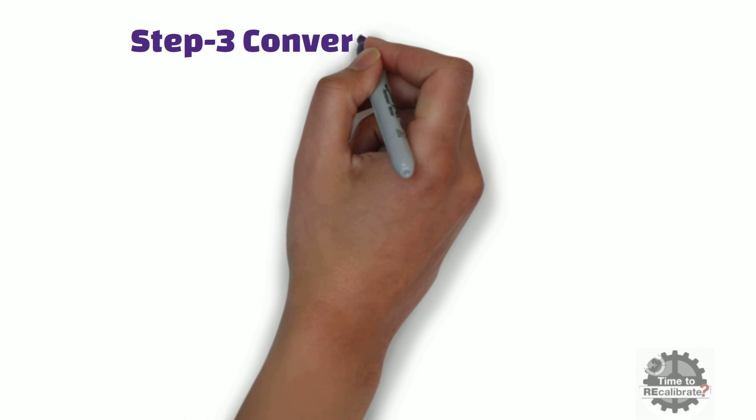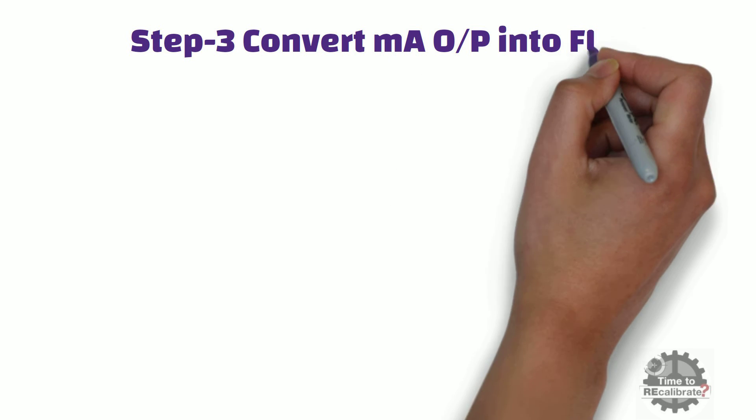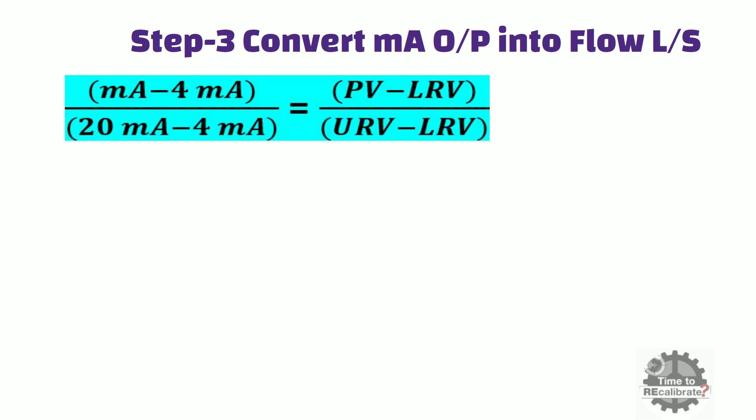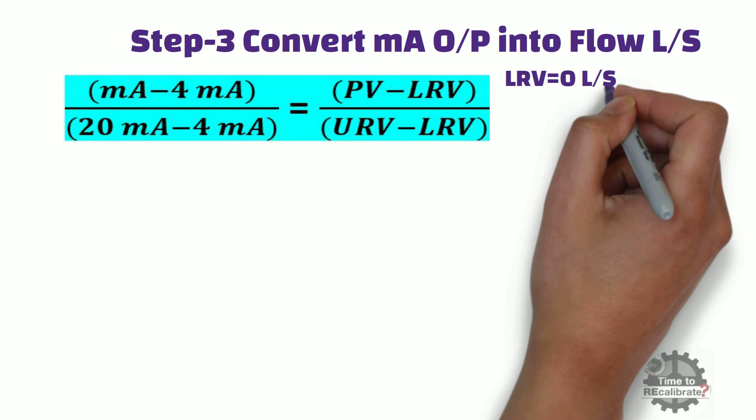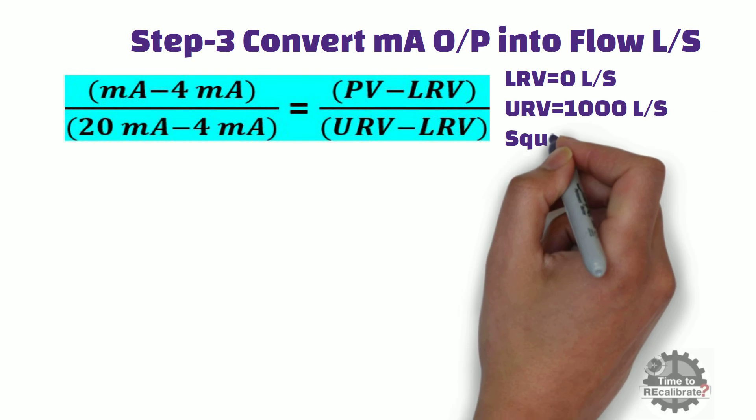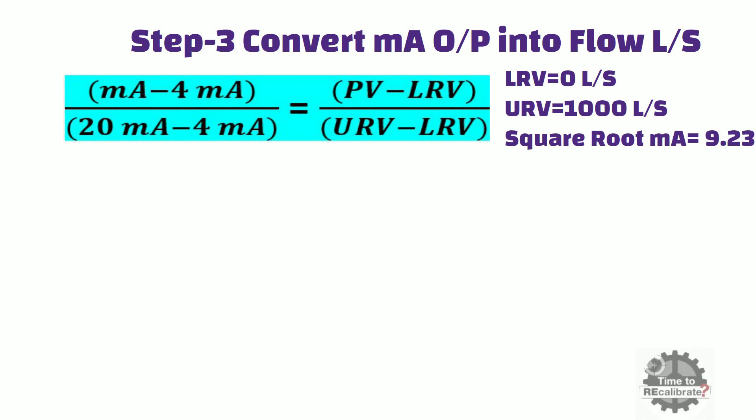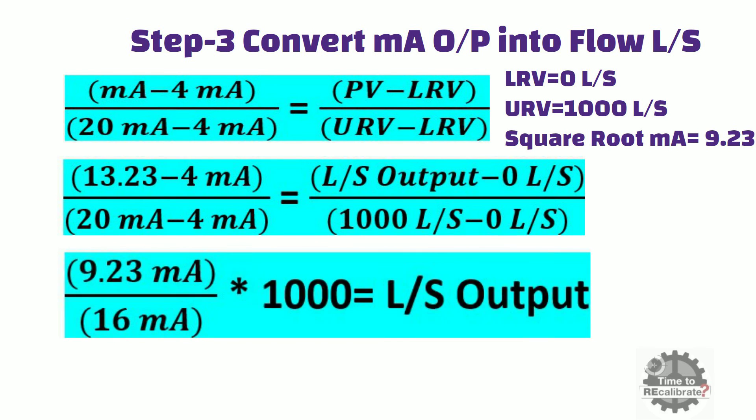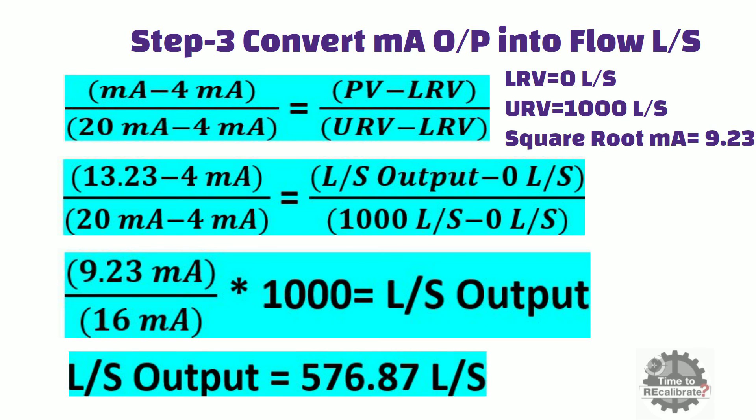In the third and last step, I am going to convert square root milliampere output into corresponding flow. As you can see from the equation, we need to put upper range value, lower range value, and square root milliampere value in the equation. Now do the simple math calculation after putting values into the equation. You will get 576.87 liters per second. This is our flow range when differential pressure is 500 mm H2O.